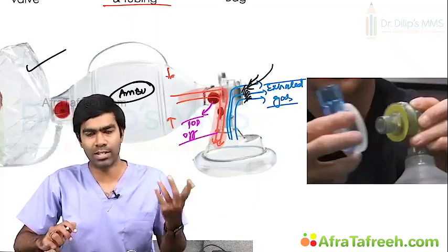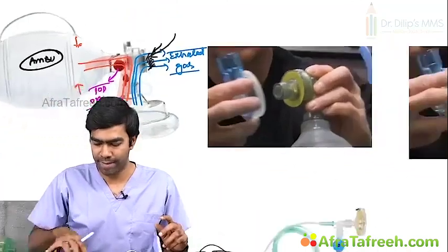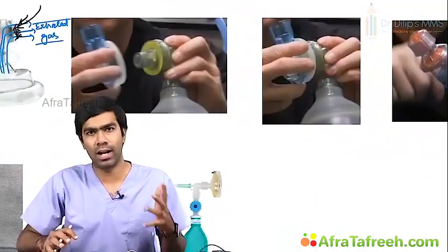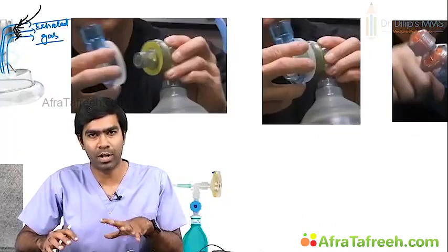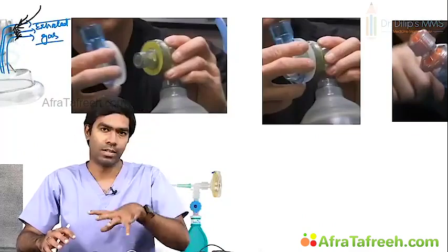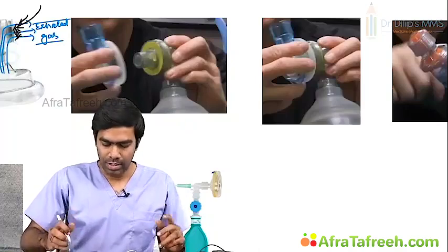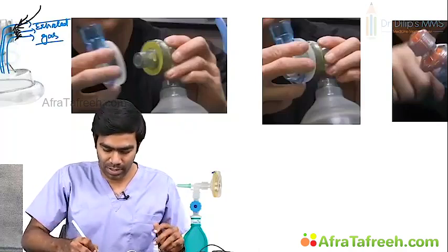To attach a PEEP valve, you need a separate thing called a diverter. Let me show that. How to attach a PEEP valve to the Laerdal device, because this is what is commonly available in many of the hospitals in the country. That's why I want to show this. Initially, you need to have something called a diverter.